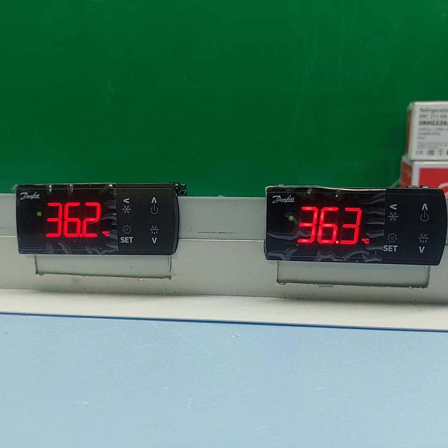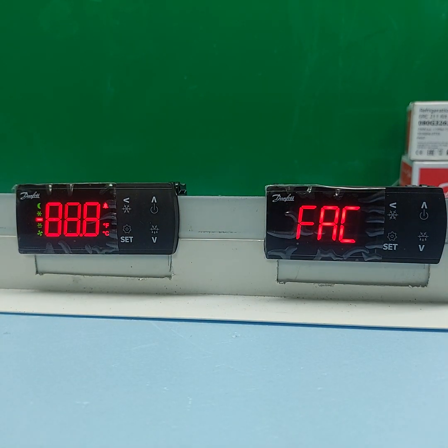Now, no need this setting, and you find some ERC with many fault setting, wrong setting. Go to factory setting and previous menu, and set as you like. Power off, then press this two button, up and down button, press, then power on, factory setting. Now the ERC with the factory setting, previous menu showing. Now you can set as you like. Okay.